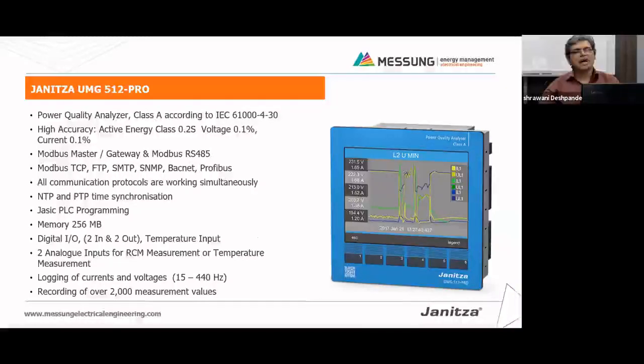The reason is simple. Why is the electricity board or utility going for the Class A meter? They just want to know what kind of power quality they are supplying to the customers. If there is no problem from the utility side and the grid is getting distorted, then naturally the problem is from the customer side, that they are distorting the grid of MSEB or any private utility, and obviously the utility suffers because of your power problems.